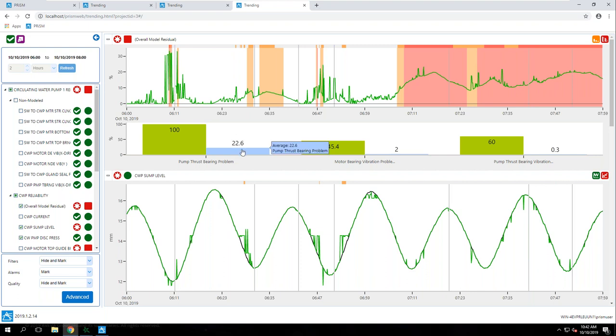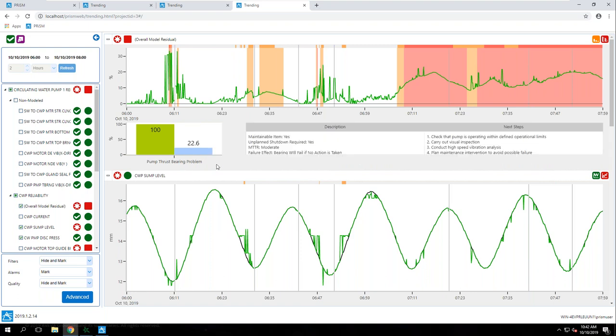As that blue bar starts to grow, you can have pretty certain confidence that that's the type of failure mode occurring. Now, if I click on that failure mode, this pump thrust bearing problem, we actually give you prescriptive information as well. Built into our model templates, we can put in things like a description of what this failure mode means, as well as next steps you would take to carry out an inspection, perform maintenance, whatever the next action should be for this particular piece of equipment.